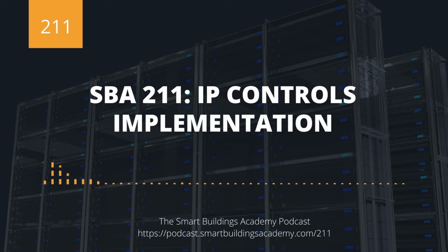All right, so there's really three ways we're going to implement IP controls on our new projects. There's the star pattern, there's the daisy chain pattern, and there's the ring pattern. So the star pattern is your traditional design pattern that we've used to connect supervisory devices to switches, right? It's just a regular Ethernet patch cable between the access port on a switch and the network interface card on a supervisory device, except in this case, it's the network interface card on your field controller.